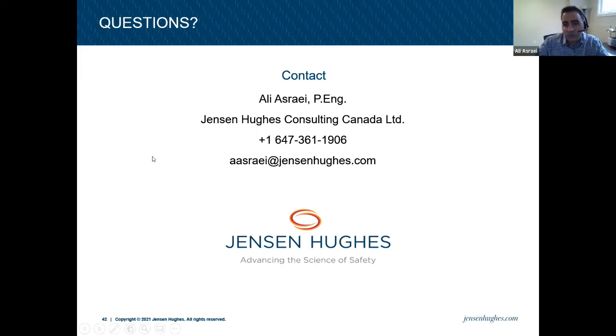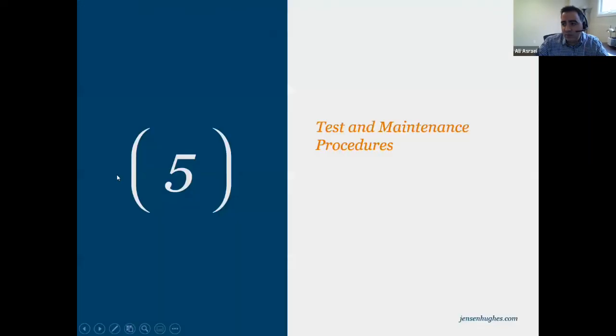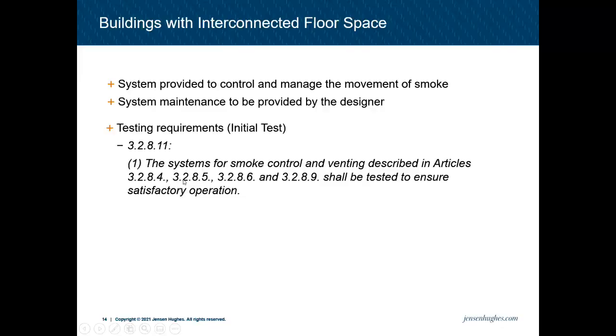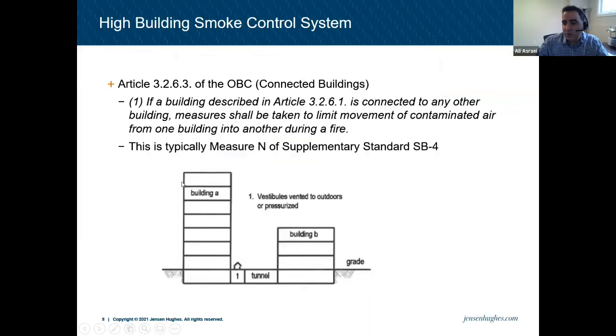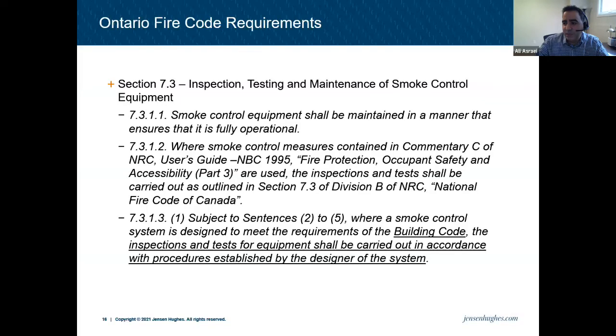So if I switch back, you still see my screen for this presentation, right? Yep. So this is all 7.3, right? It's either 7.3.1.2, where the smoke control measures contained in commentary C are provided. They have to be done by the National Fire Code. That's one thing, but there's an overlap. 7.3.1.3 says, where a smoke control system is designed to meet the requirements of the building code, which could be part of a measure, the inspection and test of equipment shall be carried out in accordance with procedure established by the designer of the system.